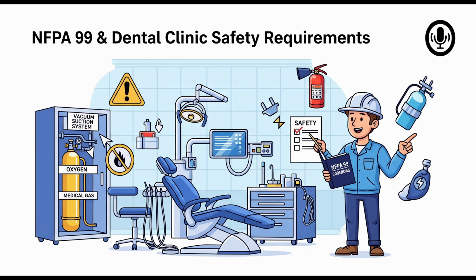So if you can have a single air compressor, how do you know if it's working correctly or if there's a problem? What about monitoring and alarms? Monitoring is absolutely essential, even with simplex systems. Section 5.3.9 covers warning systems for Category 3. And here's another difference. It permits a single alarm panel.